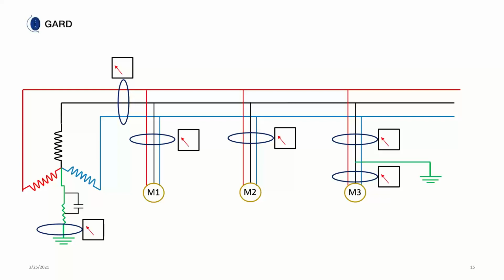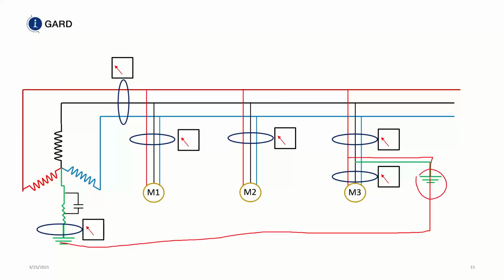We have a ground fault on C phase. The ground fault current path is here. This is the bonding network. Don't think of ground. We don't use ground as a return path, but this is the bonding network that we have, and that doesn't change regardless of what type of grounding system you have.